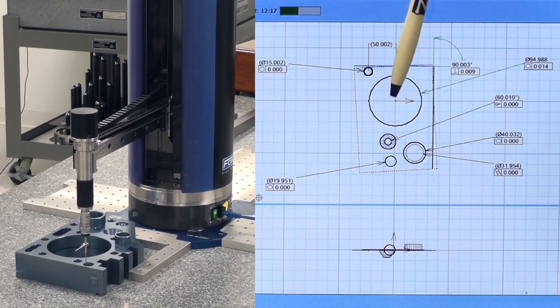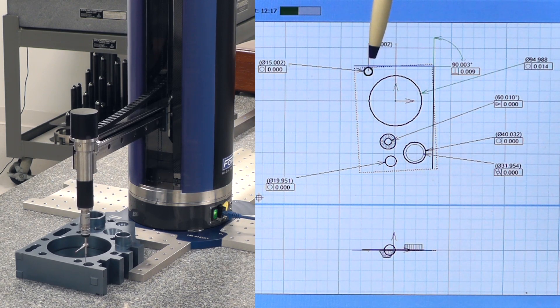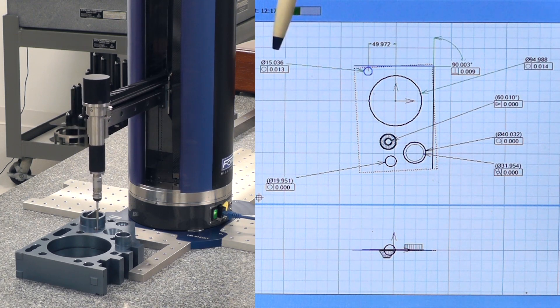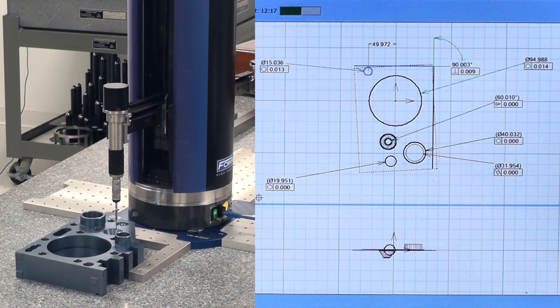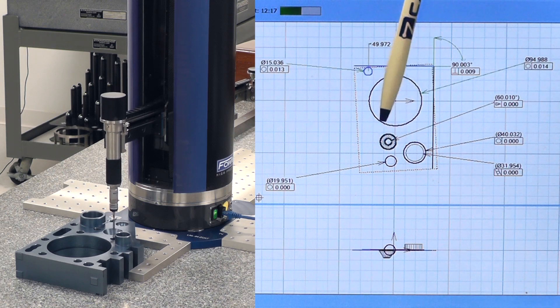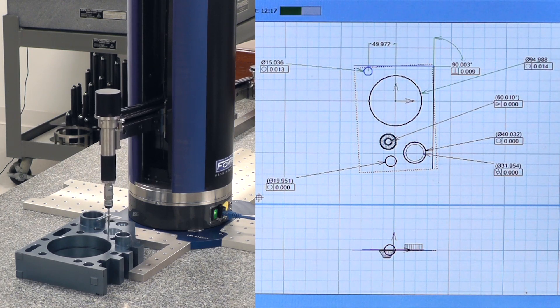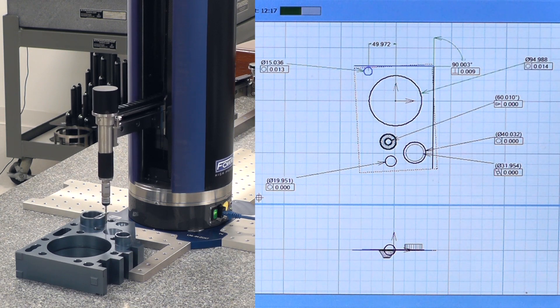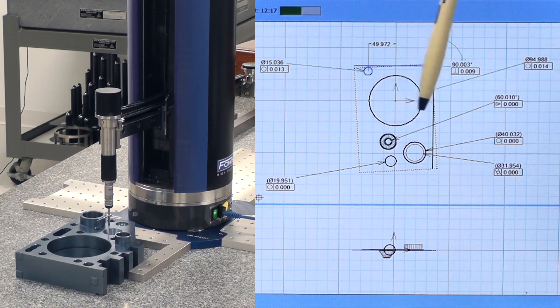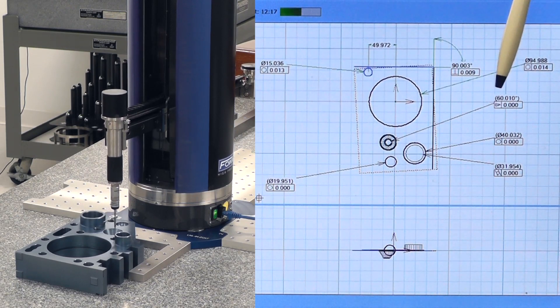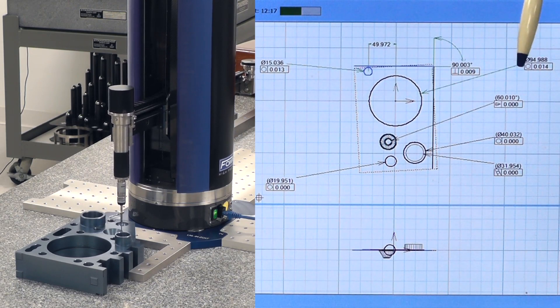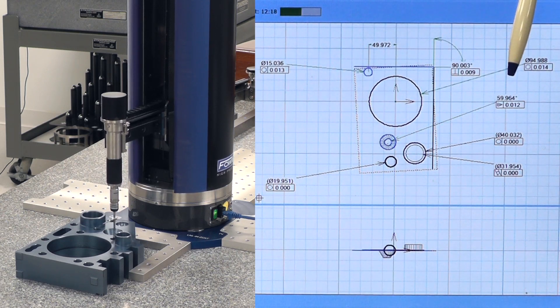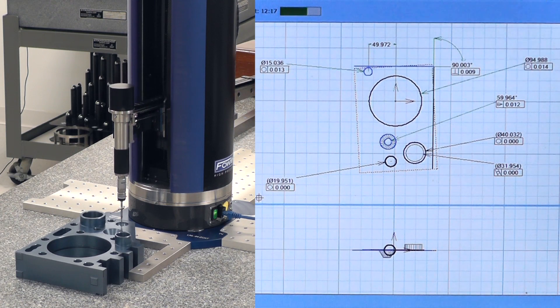Now it's going to be measuring a diameter. On the screen you can see it highlights in green where it's measuring. There's a small red dot. It shows exactly where the probe is. When it's finished, it will update the diameter of that hole. Now it's going to go over and measure this cone. It's highlighted in green. It's taking multiple probe hits in different positions around that cone. And as soon as it's finished, it will update our numbers here. It was 60.01. We'll see what the next one is when it's finished. 59.964.